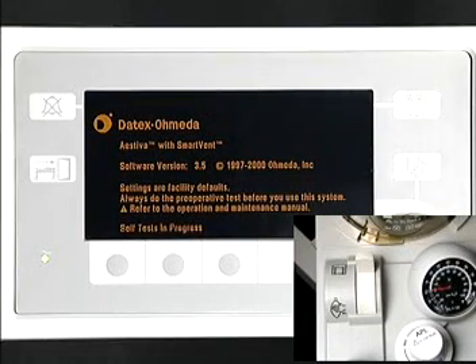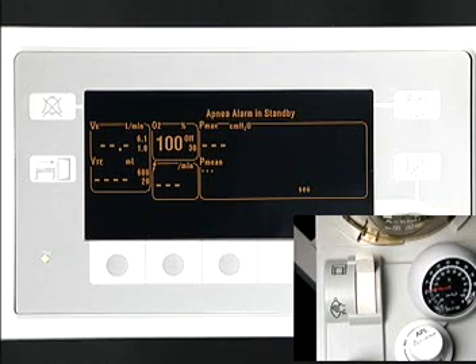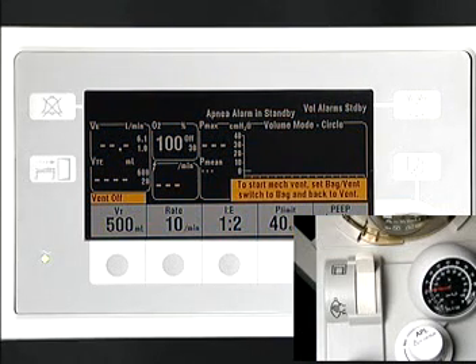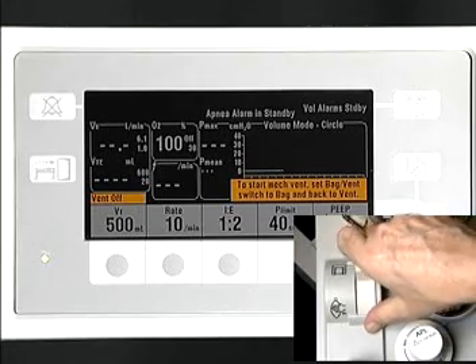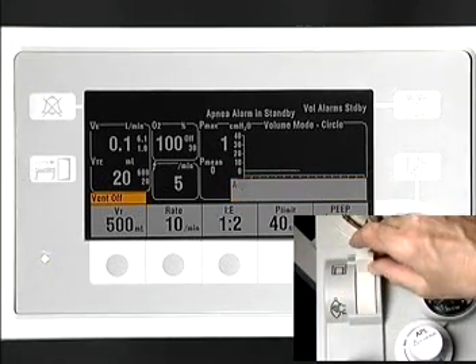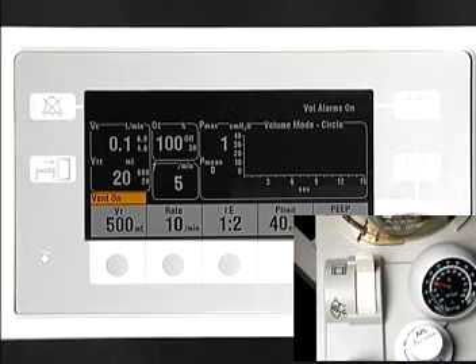Battery life of 30 minutes is available if mechanical ventilation is in use and can be extended by moving to the manual bag mode and reducing the brightness of the screen via a menu selection. If the system is powered up with a switch in the mechanical vent position, the system remains in the bag mode until the operator confirms the ventilator settings by moving the switch from the vent position to the bag position and back.